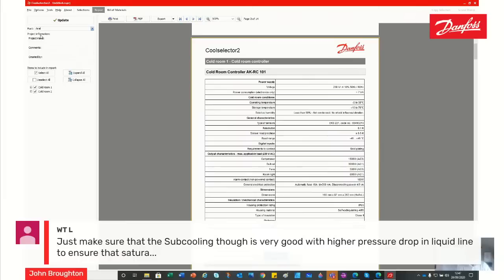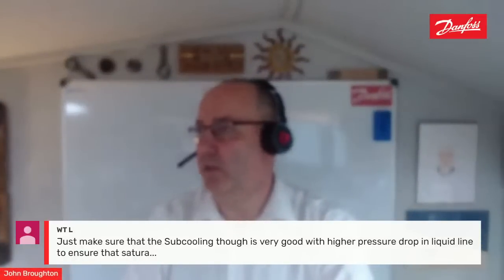I get asked this question quite a lot regarding sight glasses. Oh, I can see bubbles. Okay, maybe it's flashing, maybe it's not, maybe it's a little bit low on charge. The best place to put a sight glass is in front of your expansion valve or your metering device.